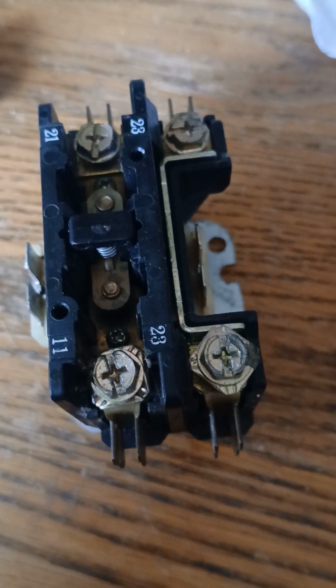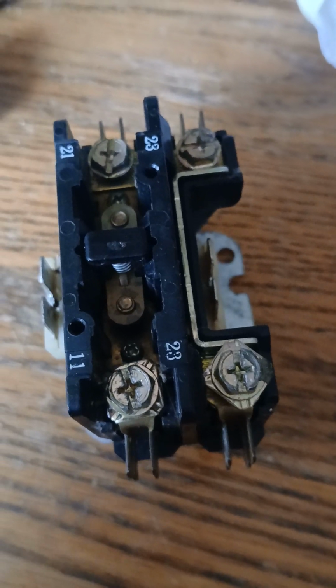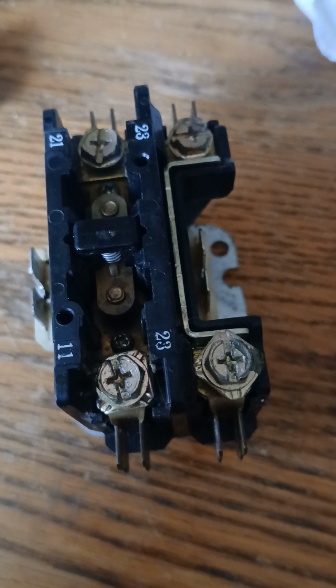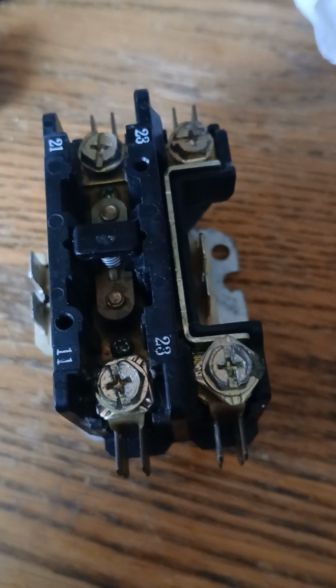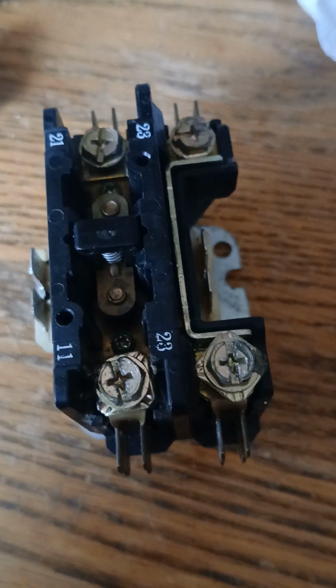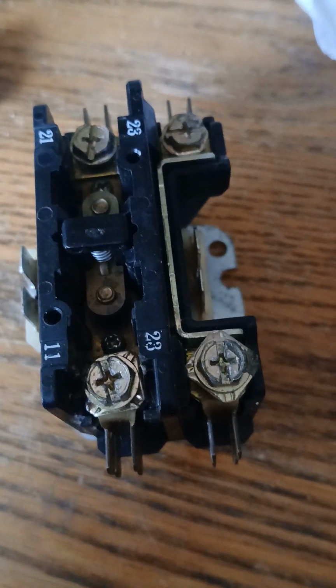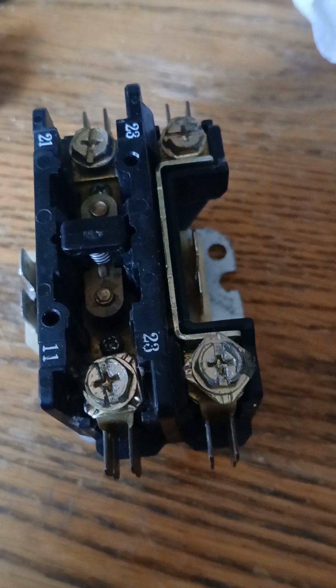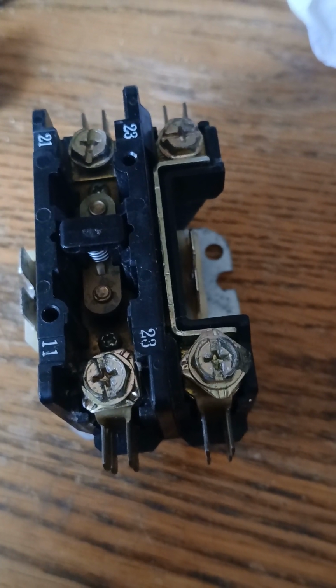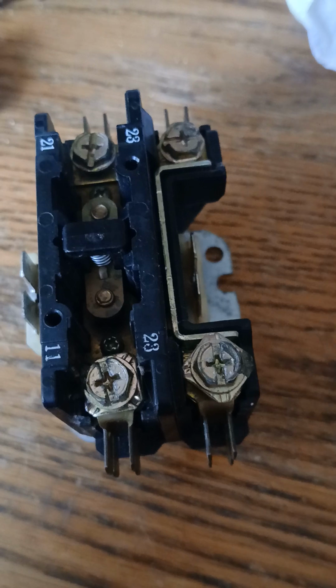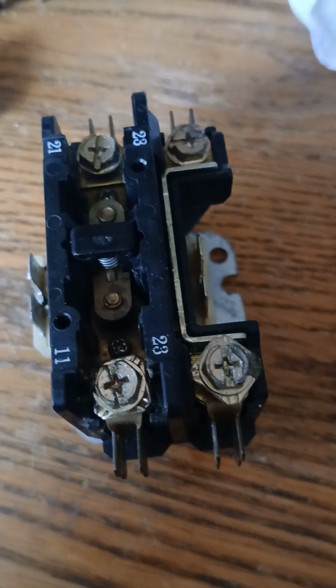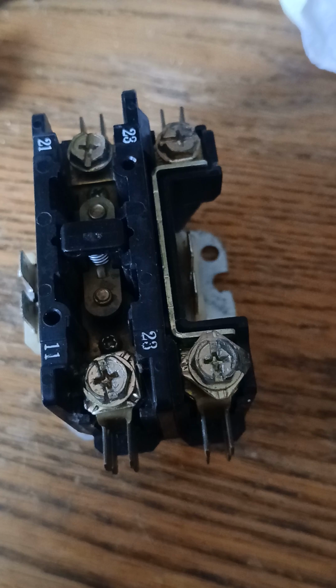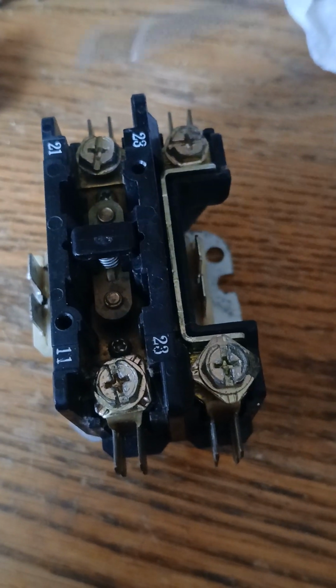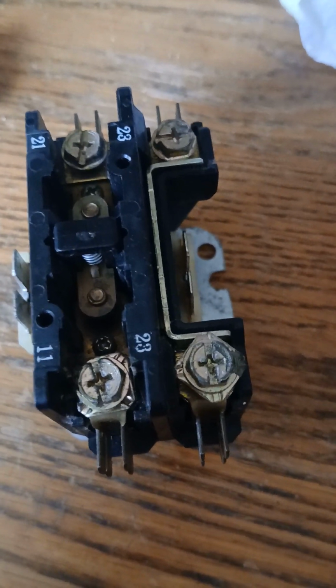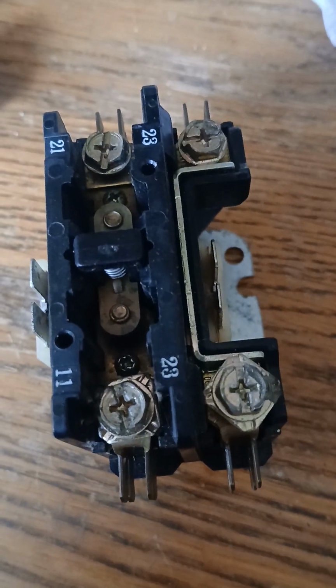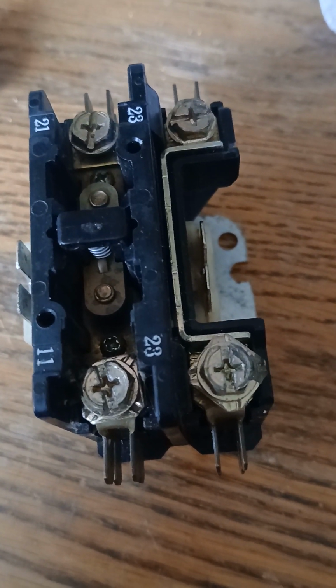I'm not certain if that's the correct terminology, but let's just say when it's energized, it pulls the contactor in. When it's de-energized, it releases it and shuts it off. This is for safety. This protects your unit. This protects your wiring, so you're not just running the system incessantly without stopping. So this is why it's good to have a contactor somewhere in the condenser to turn the system on and off via low voltage.